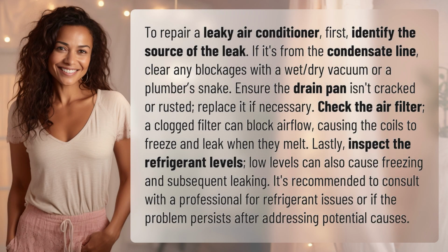To repair a leaky air conditioner, first, identify the source of the leak. If it's from the condensate line, clear any blockages with a wet-dry vacuum or a plumber's snake. Ensure the drain pan isn't cracked or rusted. Replace it if necessary. Check the air filter.